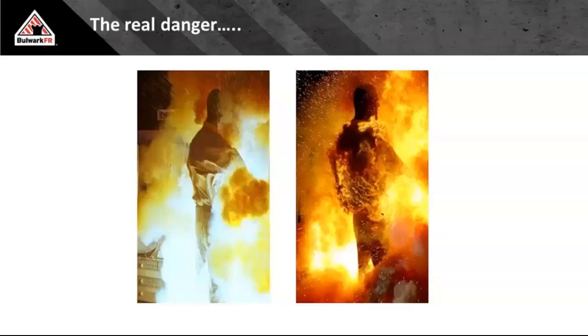On the right-hand side, what do you see? All that thermal energy that is now wrapped around that mannequin that was wearing clothing, is that clothing catching fire and now continuing to burn? So, what's my point? You have now extended that event. By catching fire and continuing to burn, the arc flash is long over, and all the injury that is now occurring is due to what we wore in front of that arc flash.